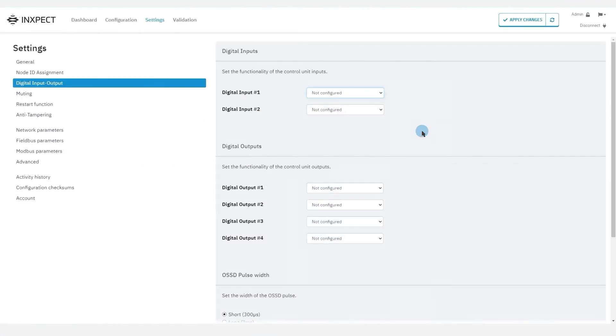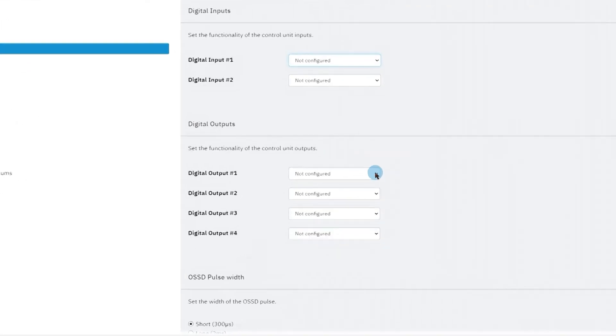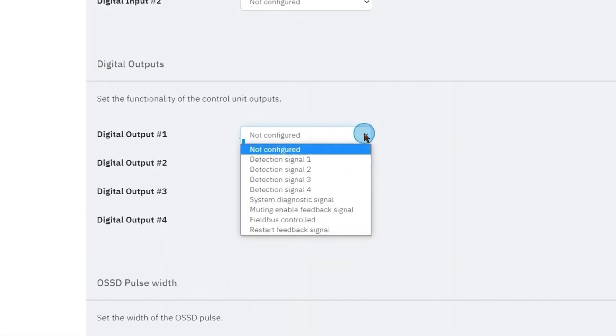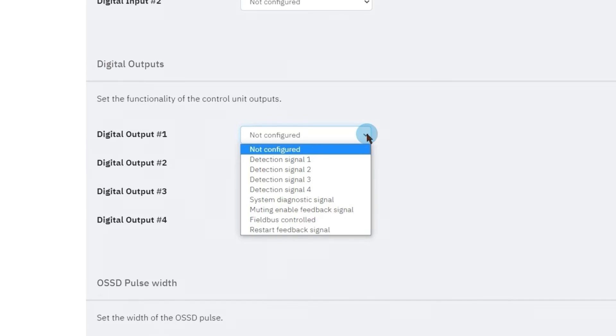Let's take a look at the output options. The four detection signals, in which each signal is useful for reporting the status of the corresponding detection field to an output. Remember that, in order to ensure the system safety level, each detection signal must be identically reported on a dual channel safety output.